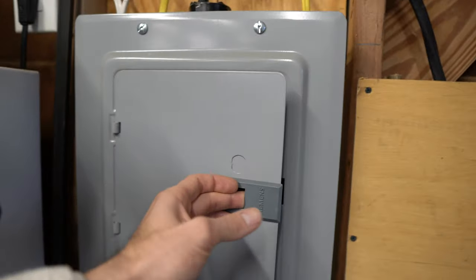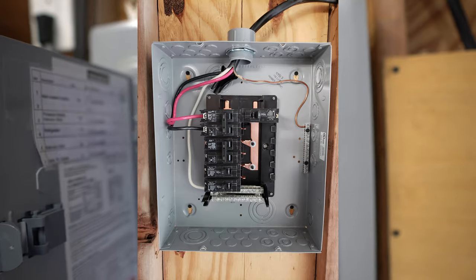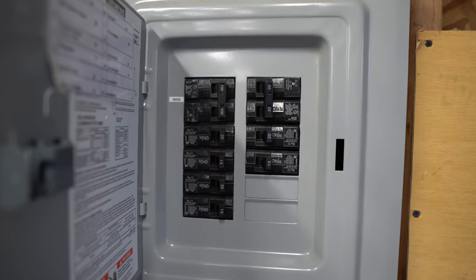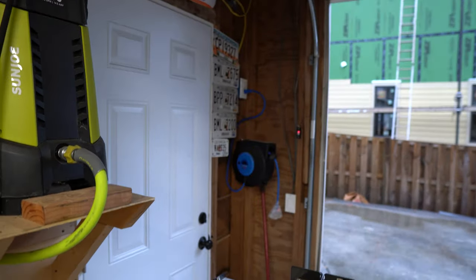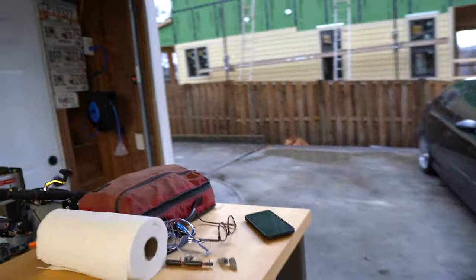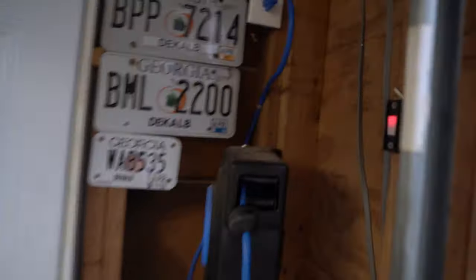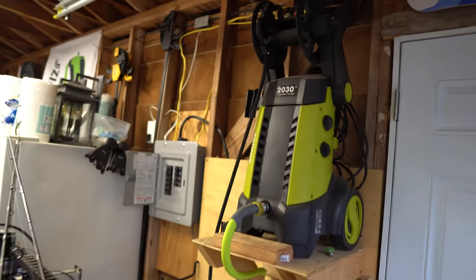I think it's 8-gauge — that big black cable — so that runs all the way to my main panel. The panel's running on 60 amps; I've got 100 amps in here now, but this really just acts as an on-off switch. Then I've got a couple 20s, a couple 15s, and then a 240V 30-amp — maybe for a welder someday. But all these are running basically just the lights, the refrigerator, and the cord reels. That's a dedicated 20-amp circuit with 12-gauge wiring throughout, so it's all legitimately run.